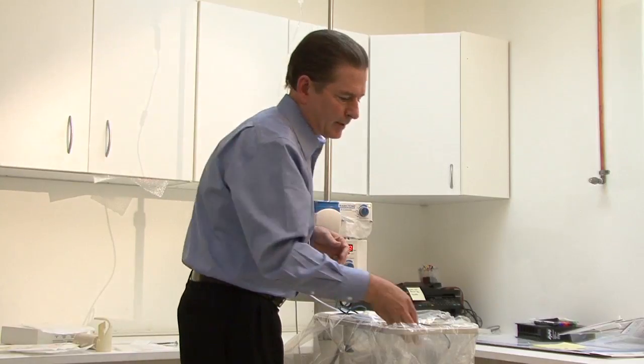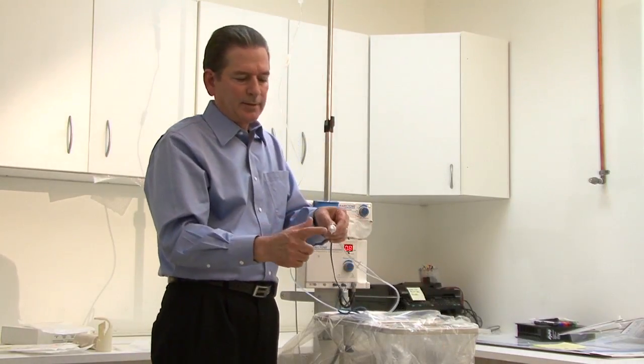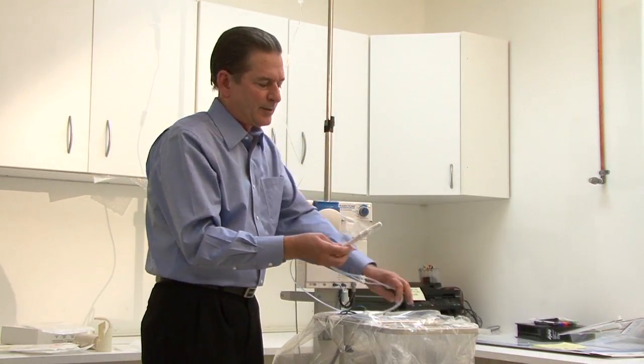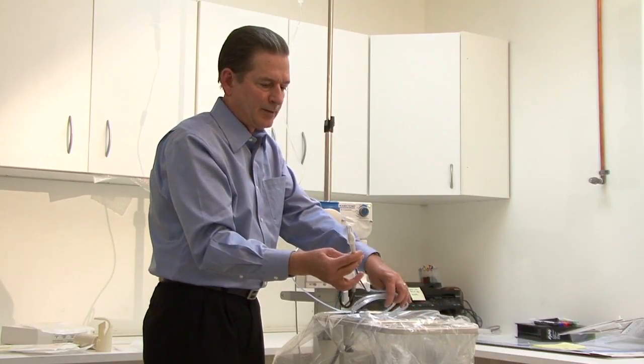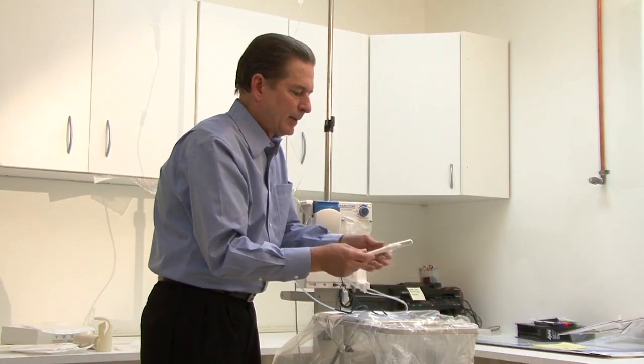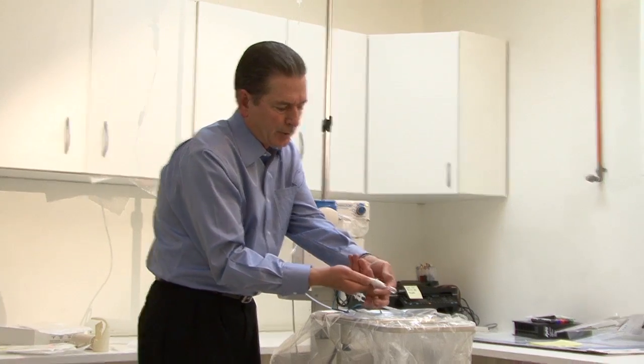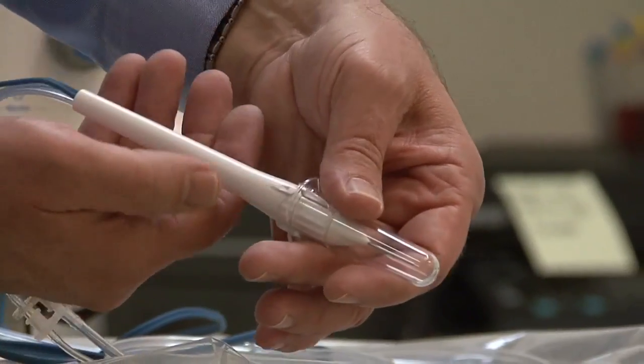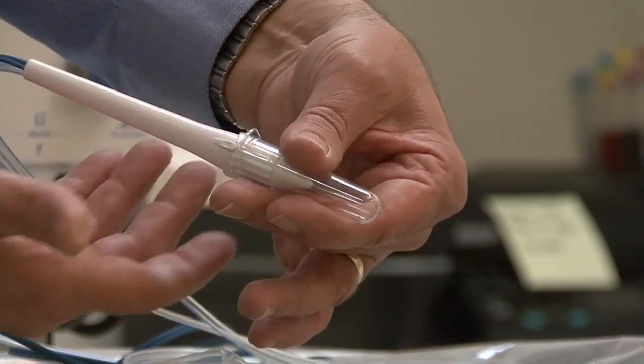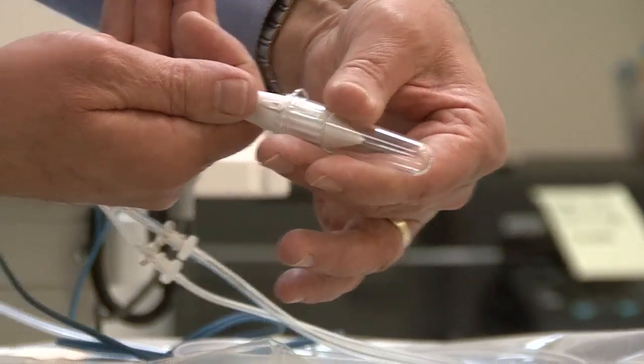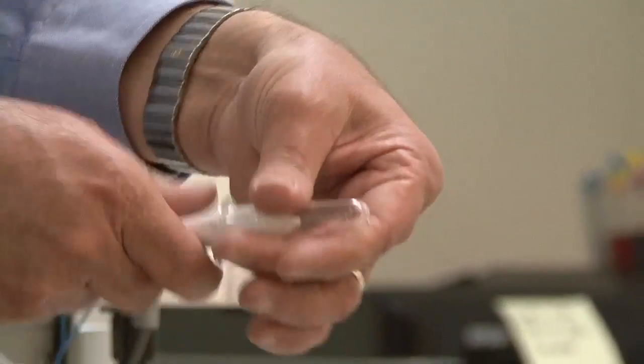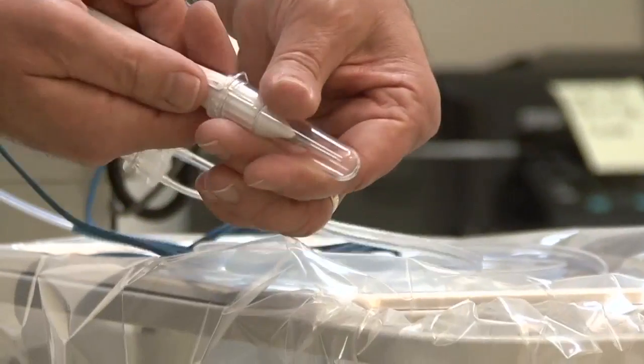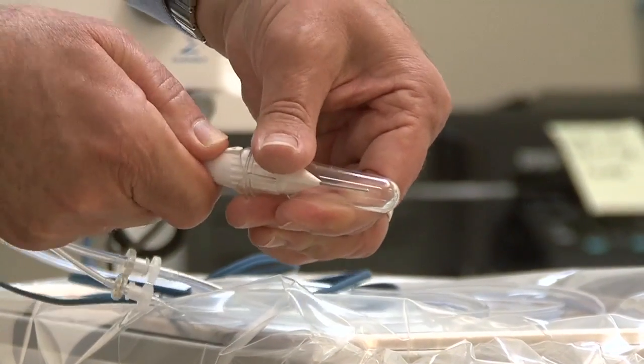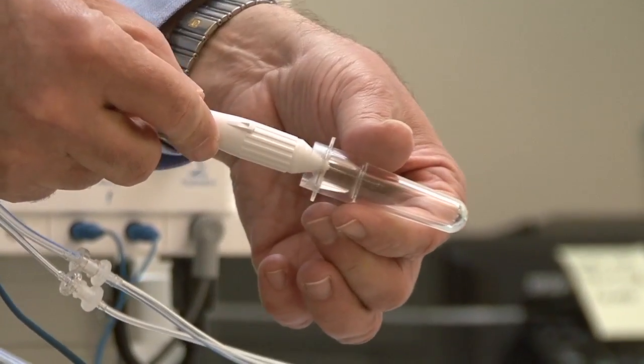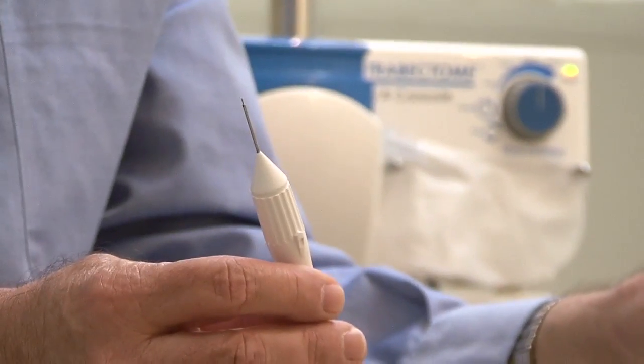And if you're scrubbed in, we mentioned that the tip is really delicate, but when it's time to actually use the handpiece in the surgical field, the cap can be removed as follows. And it's very important to remove the cap without damaging the tip. The trick to that is simply grab the cap and the handpiece. You don't need to pull on the cap, just twist. And when you twist, you'll see there's a little ramp and you'll hear a little click. When you hear that click, the cap completely releases and we can remove it without touching anything.